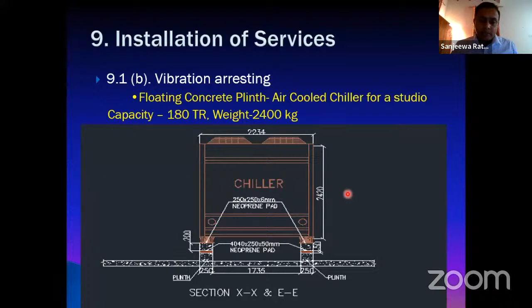Again, we have to think about these installation activities: the height of the concrete plinth. Sometimes we don't think about it. When we are designing the height of the plinth, we have to think about the drain U-trap also. The height of the U-trap is a very important factor to be considered when thinking of the height of the plinth to place this equipment. For example, an AHU or indoor unit, floor-mounted fan coil units. You have to calculate the length of this U-trap. Correctly sizing this drain trap is very important, otherwise unexpected problems come.